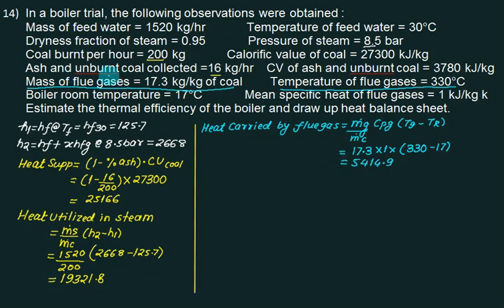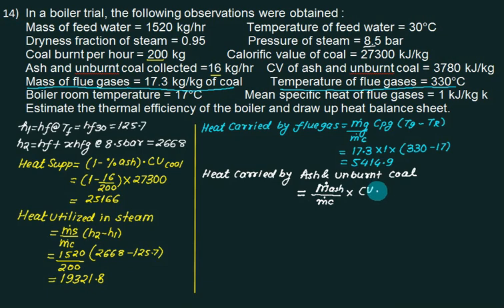Heat carried by ash and unburnt coal. Check: is it also given as 16 kg? Yes. Mass of ash divided by mass of coal multiplied by calorific value of unburnt coal. Mass of ash is 16 divided by 200, and the calorific value is 3780 kJ/kg.